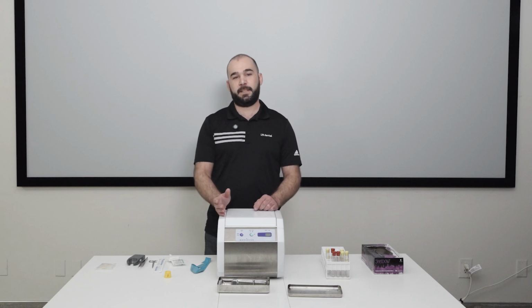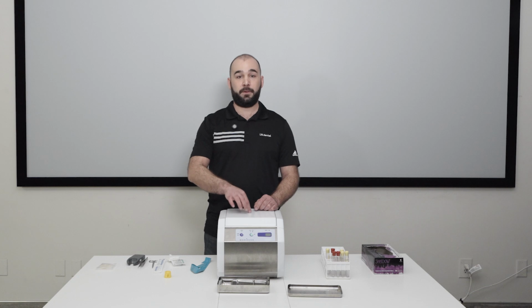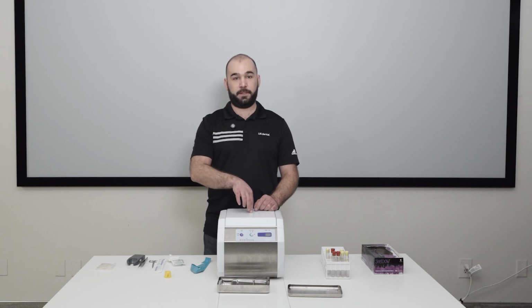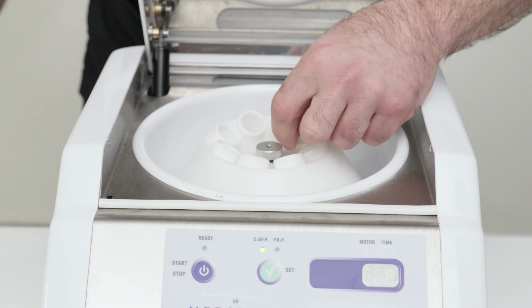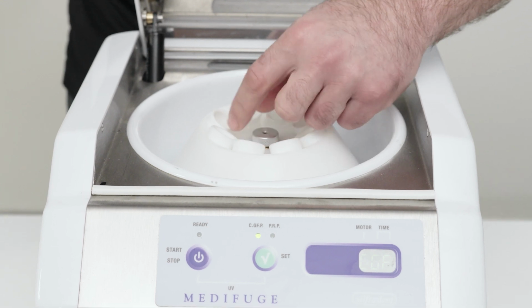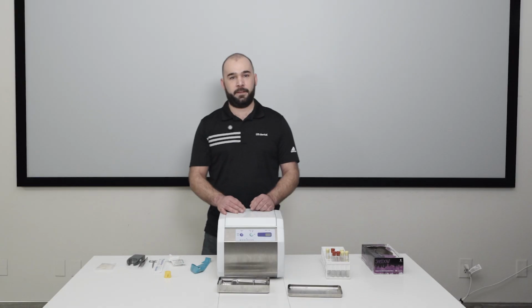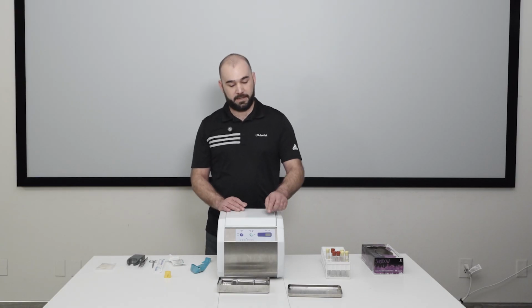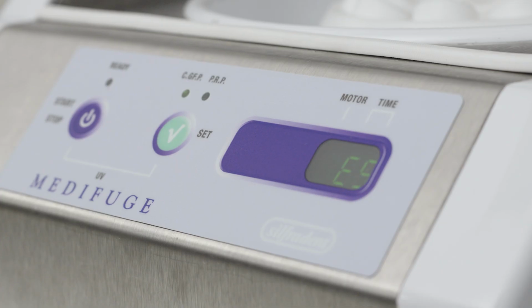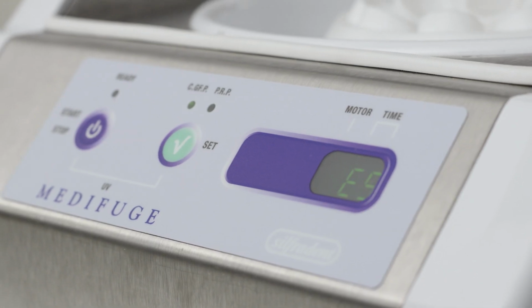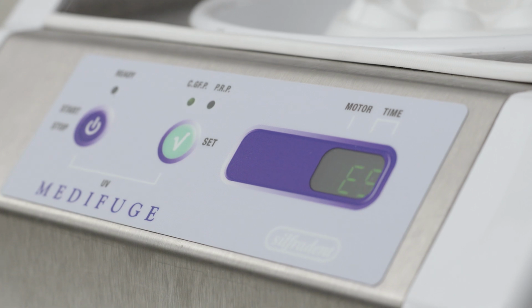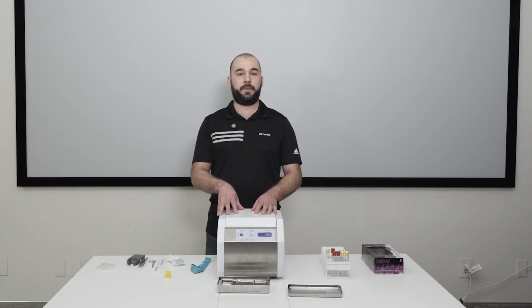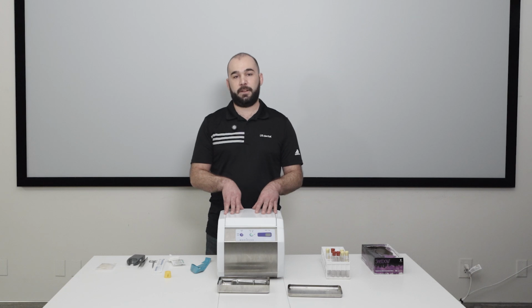Please keep in mind that the metal screw in the center of the rotor may loosen over time with prolonged use, so make sure to tighten it clockwise from time to time. If it is loose during operation, an E5 error code will appear on the display and the machine will not function properly. A very unique feature of the Medifuge is the UV sterilization function.